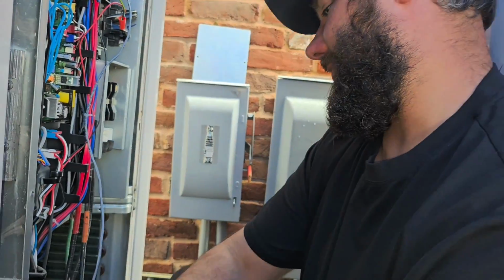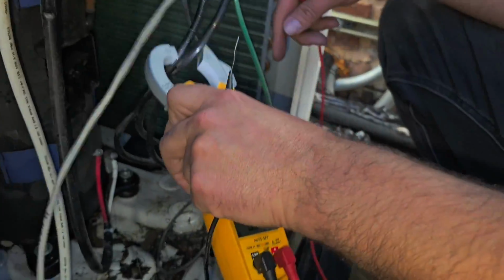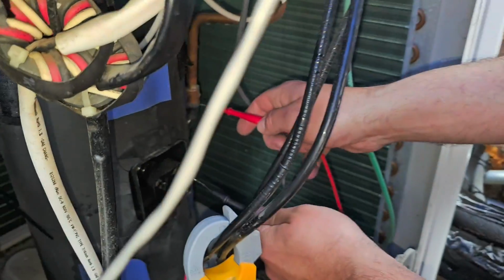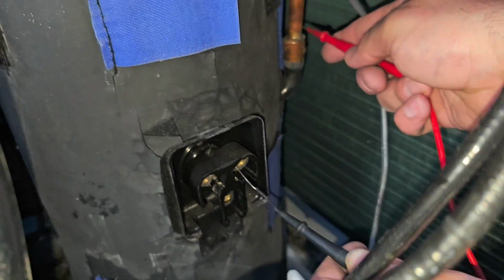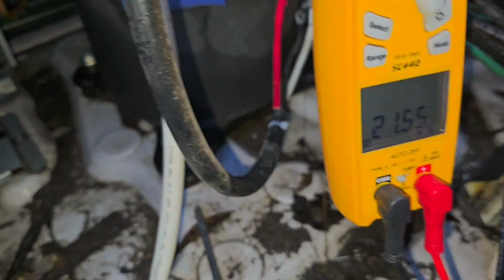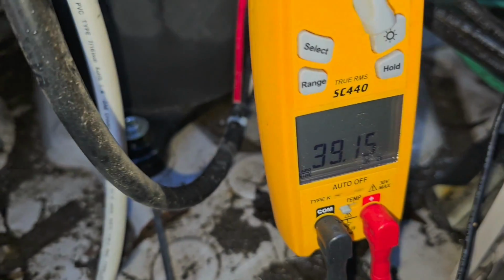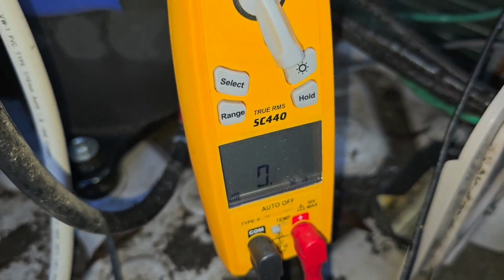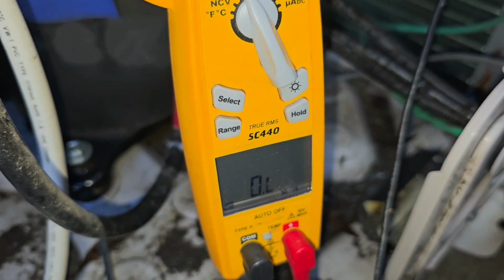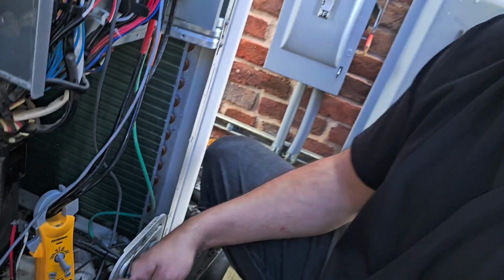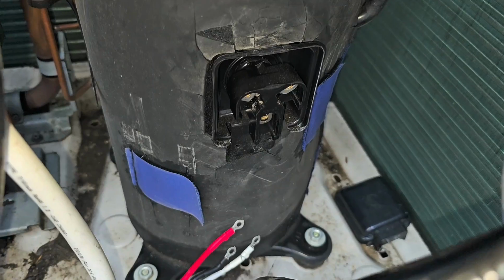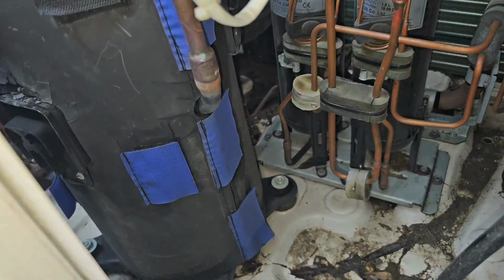Now let's check the other compressor. From each winding to the copper. Wow. And then the last reading is right there. So both of our compressors are shorted to ground. This is quite unbelievable. But I'm going to be coming back to replace 2 compressors. Yay! It's really hard to believe that these compressors are both shorted to ground.